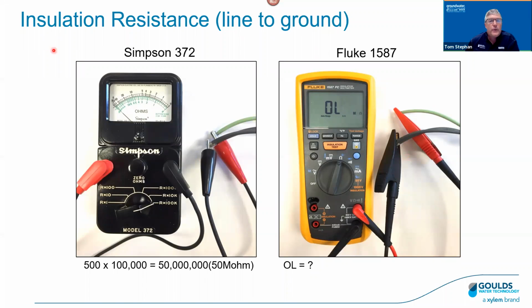Okay, so the last one here is what we call the I, or the insulation resistance, and that is line to ground. Let's take a look at the old venerable Simpson 372. The service manual is going to take you right through it. Set the dial to R times 100K, 100,000, and check hot to ground, with no power, disconnected. With this meter we have to do some math. You probably can't see it, but this has pegged the meter, and it's a brand new motor. It's pegging the meter at 500. Remember, we set the scale to R times 100K, so you multiply that by 100,000 and you come up with 50 million ohms, or 50 megohms.